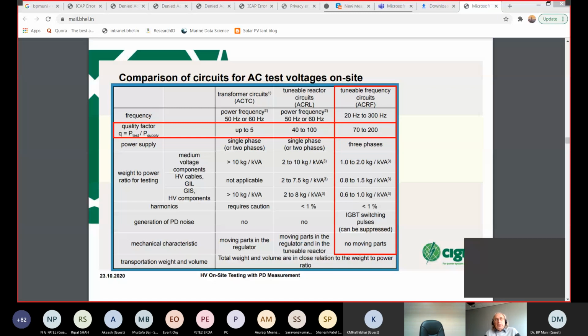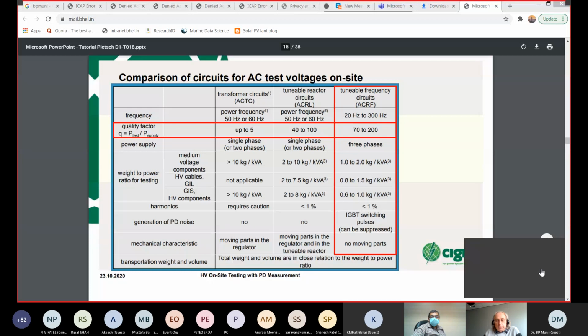Of course, if your cable is quite short, let's say 1 kilometer or so, then you can definitely also use maybe a compensated transformer or whatever, if it's available and if you have the power available on site. And due to the Q factor, which shows the test power, it's much more reduced by a factor of 100. So that means if you only need 1 MVA and you use a resonant test system, then 10 kVA is sufficient. So you can get it right off the power supply. You have it in your house, so to say. And that is a big advantage of using a resonant test system. It has nothing to do with the test object itself. It has only to do with the capacitance and the power you need.